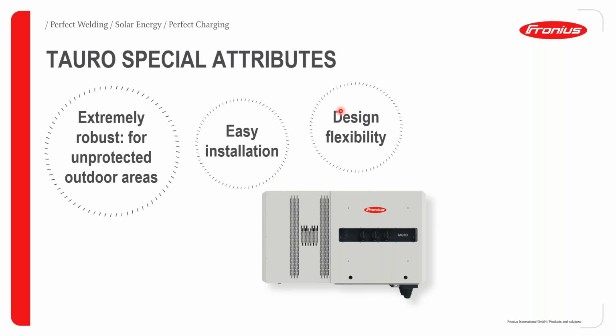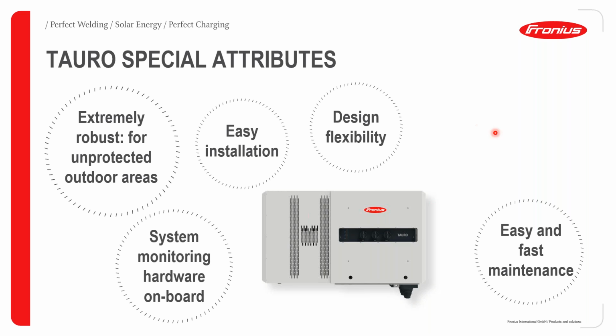This inverter will have a maximum of 3 MPPT, and therefore, in terms of flexibility of design, this is something that would be very unique to the Fronius Tauro series. Ease of maintenance: the power stacks will be very easy to remove and to refit, and therefore we do envision a situation whereby each Fronius Tauro inverter can be maintained by a single technician on site, depending on which spare part has to be replaced. And then system monitoring and hardware, everything is on board, just like the Fronius SnapINverter and Gen 24.